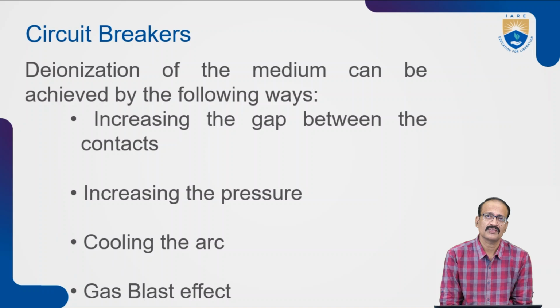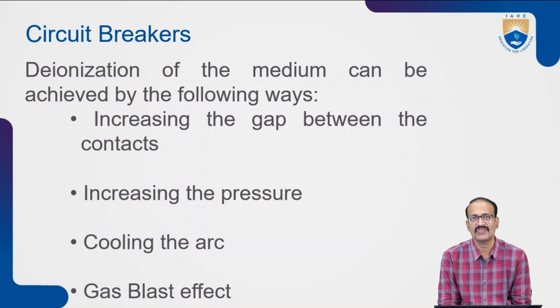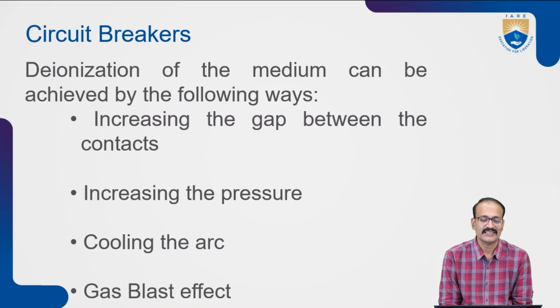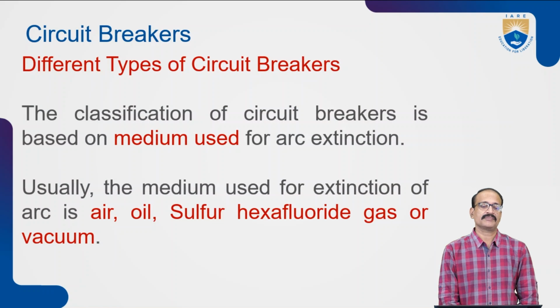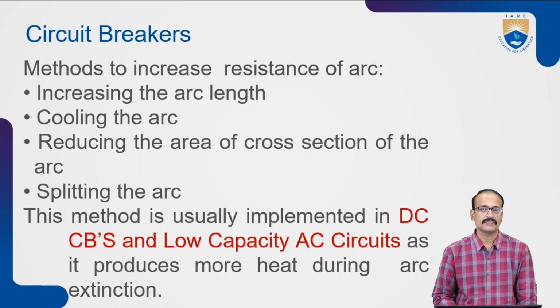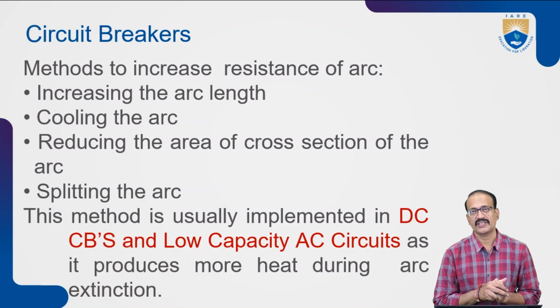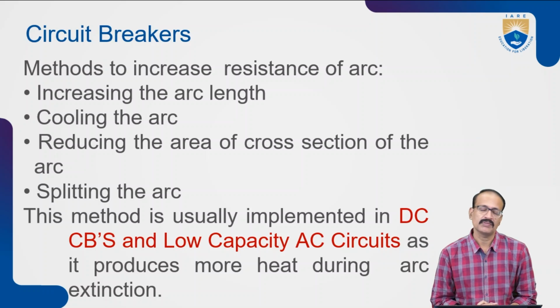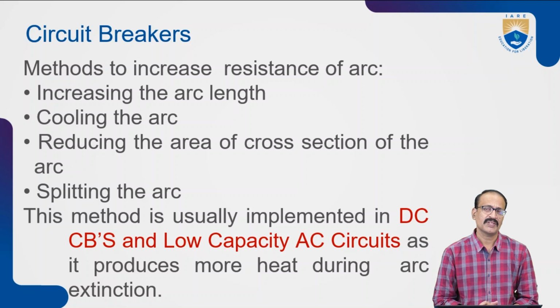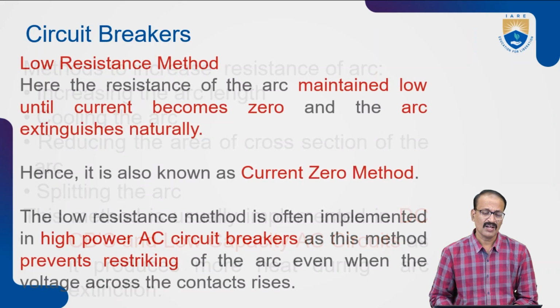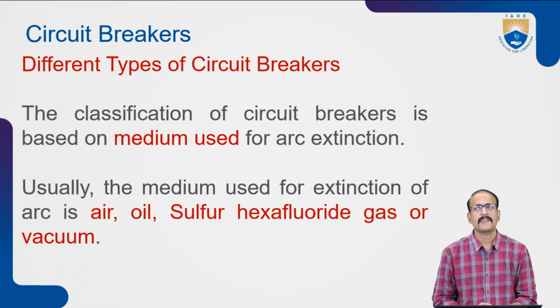So for the deionization process, we have to increase the gap between the contacts, increase the pressure, cool the arc, and also use a gas blast. So these are the methods for controlling the arc, for extinguishing the arc as quickly as possible: the low resistance method, the high resistance method, and deionization. And there are many types of circuit breakers based on the medium we are using. They are air, oil, sulfur hexafluoride gas, or vacuum circuit breakers, and we will go through these circuit breakers in detail in the next class.